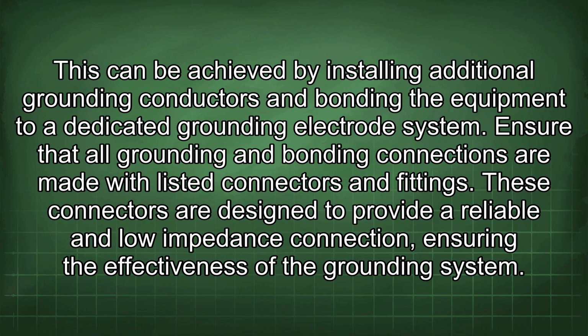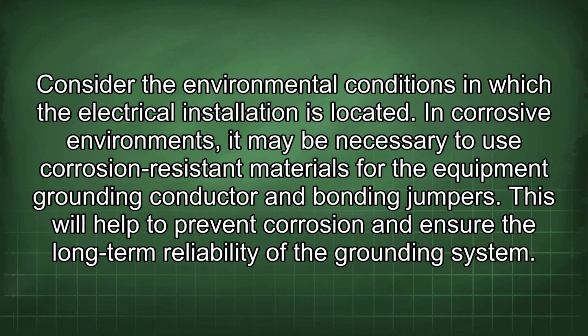Ensure that all grounding and bonding connections are made with listed connectors and fittings. These connectors are designed to provide a reliable and low-impedance connection, ensuring the effectiveness of the grounding system. Consider the environmental conditions in which the electrical installation is located. In corrosive environments, it may be necessary to use corrosion-resistant materials for the equipment grounding conductor and bonding jumpers. This will help to prevent corrosion and ensure the long-term reliability of the grounding system.